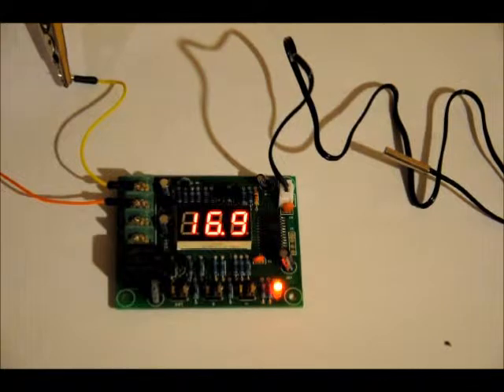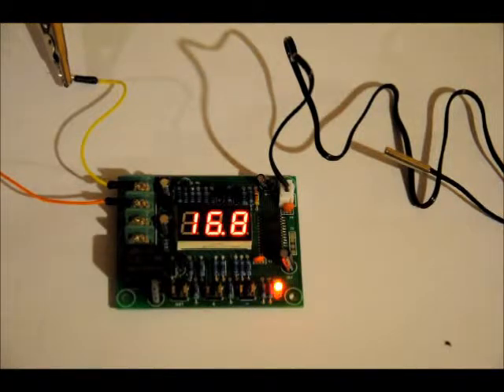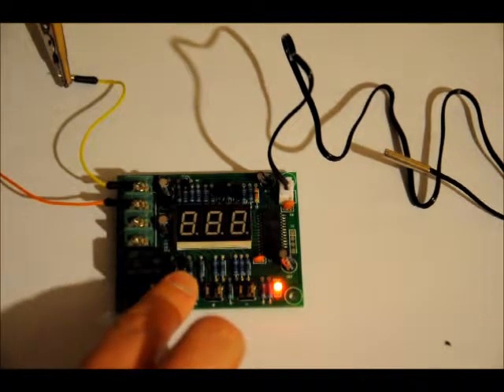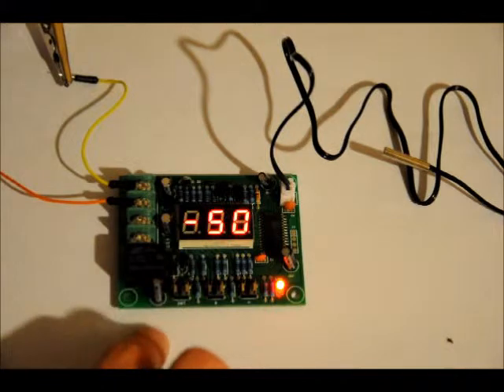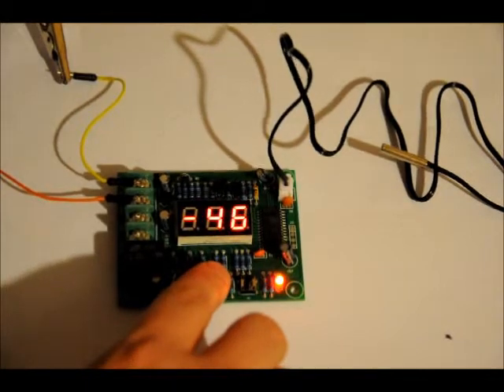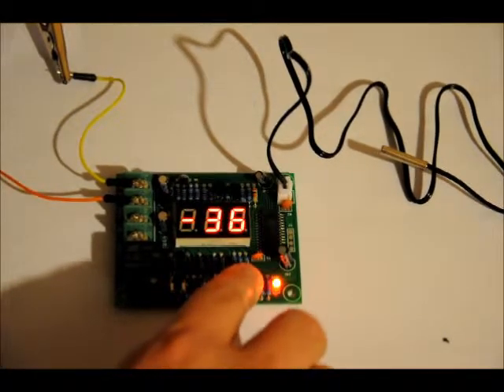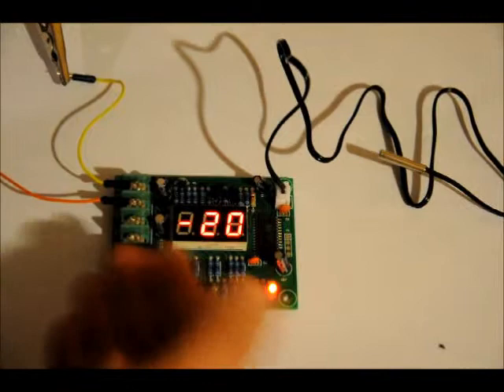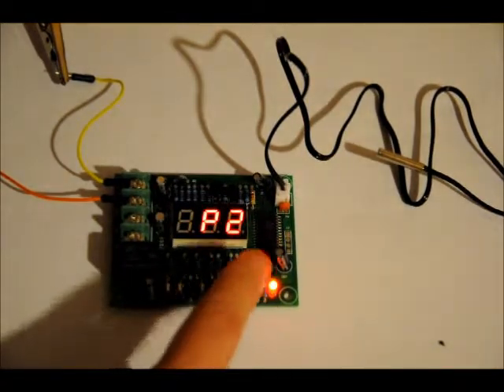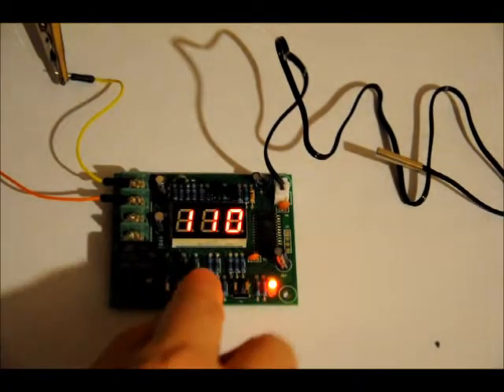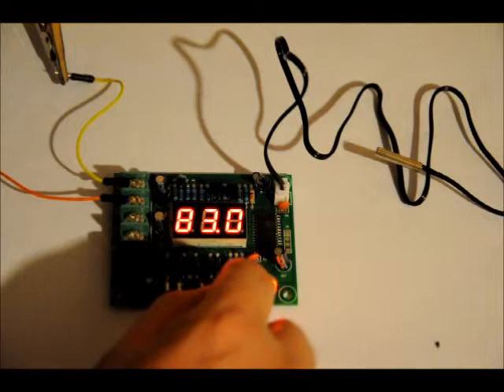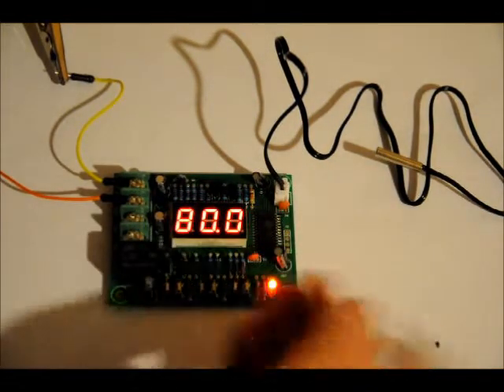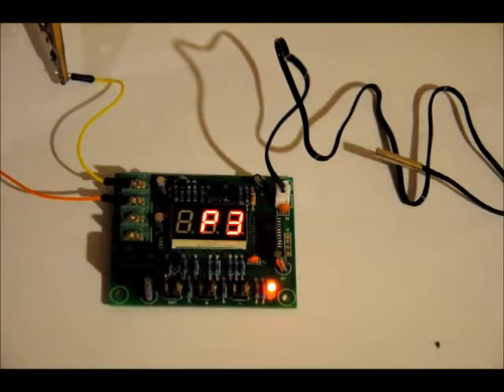Now, one thing. If my video is not explaining this well enough for you, I will be writing up a quick manual in the listing. So don't worry too much. Leftmost button will bring us back to the program modes. Let's go to P2. This is our minimum setting. As you can see, it cannot exceed 50. So this is our minimum operating setting. And so you can set, let's set it at negative, this is our negative operating setting. Meaning it won't operate at temperatures less than negative 20 in this case. So press back. We go to P3. 110 being our absolute highest temperature that this will operate at. Obviously things will start to melt if you get any higher than that. So let's say our highest operating temperature is 80 degrees. So negative 20, 80 degrees. So that's all the P2 and P3 does.